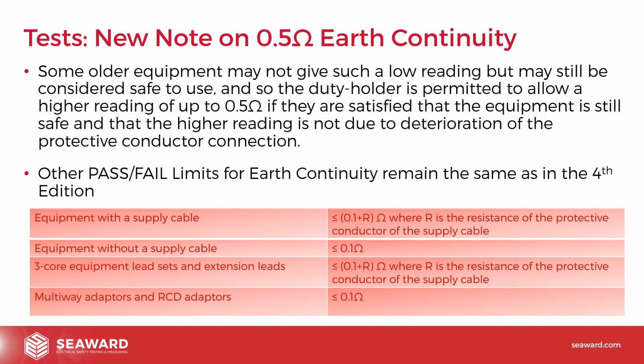Now, the aim was to put this in the table and just say older equipment, 0.5, but then what is old equipment? How is it defined? So it was quite confusing. So we argued quite strongly in the committee and got it reduced down to just a note. So there is a note in there that says for older equipment, the duty holder can determine and say, actually, we're happy with this 0.5 ohm reading. It's not really a change to the code of practice. It's just the code of practice now recognising that there was some old equipment, to very old standards, that may actually be higher than the 0.1 plus R, so they've included this in.